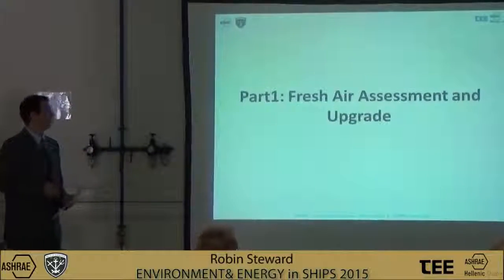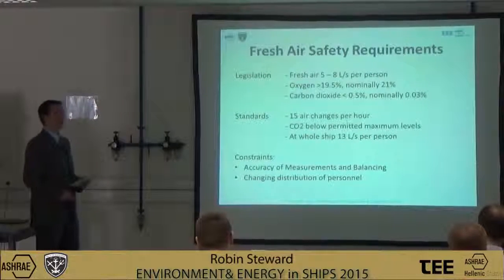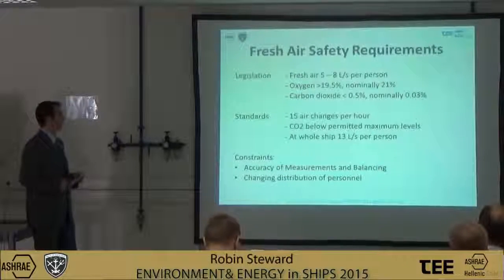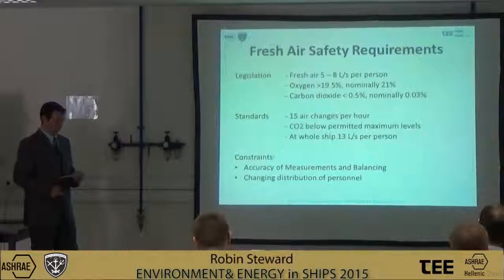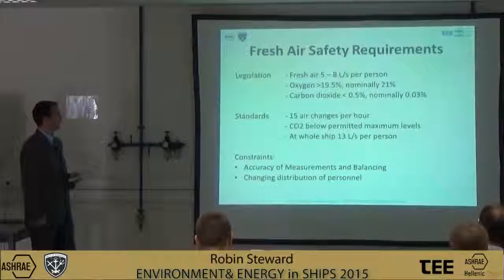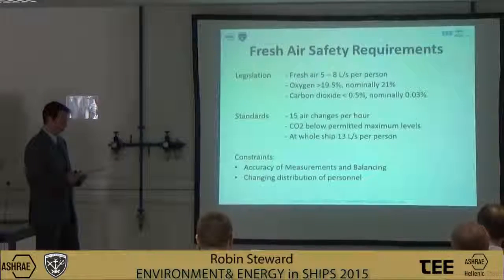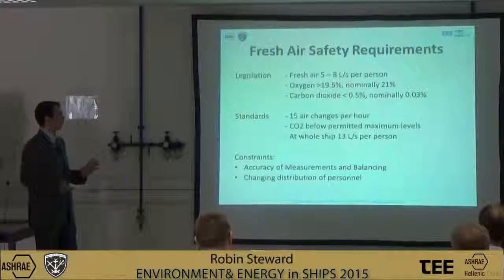Part one of the presentation covers the fresh air assessment and upgrade. I'll walk you through the safety requirements applicable to these Navy ships, and we've assessed the flow rates of the ship against best practice. The UK Workplace Health and Safety Welfare Regulations of 1992 stipulate 5 to 8 litres per second per person within the ships. The naval standards recommend a whole-ship average of 13 litres per second per person.